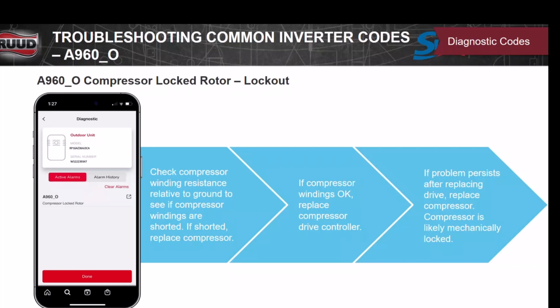A960_O, we want to check the compressor winding resistance relative to ground. If you have a grounded compressor, I have seen one of these compressors run with a grounded compressor. Yep, it had a grounded compressor, and it was running. But it would just overheat really fast and cut off. We want to, at this time, check the compressor, check all the windings to ground, check them between each other.